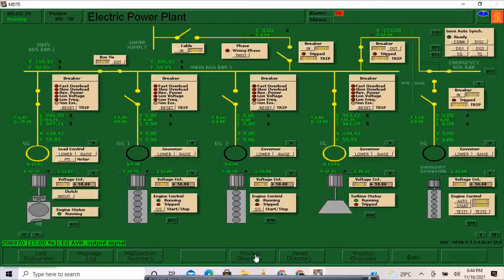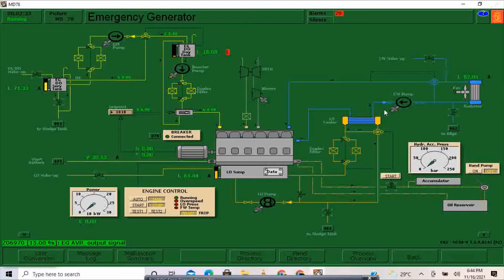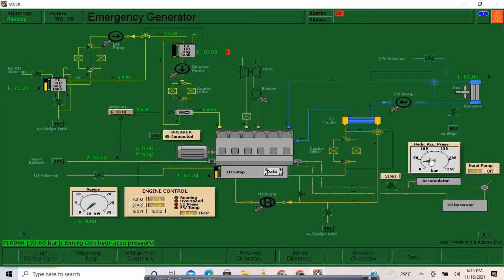I'll go to the emergency generator once again and switch the hand pump on — I will do manual hand pump. Now I'm pumping. Normally it should be around 200 bars, so at 200 bars I will stop pumping.